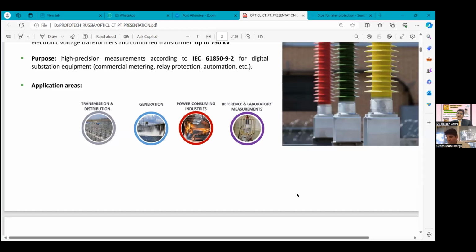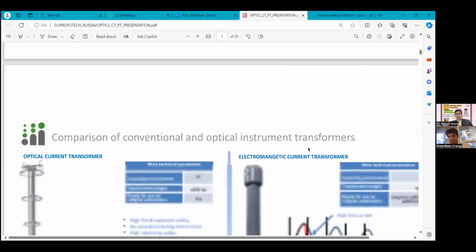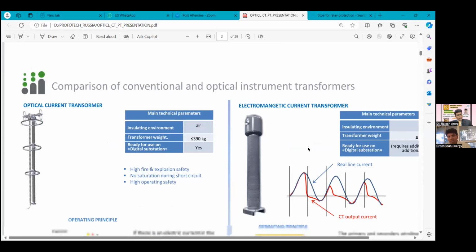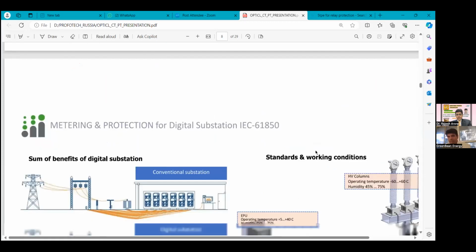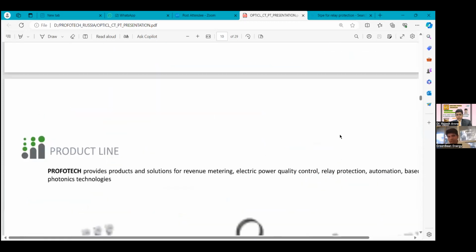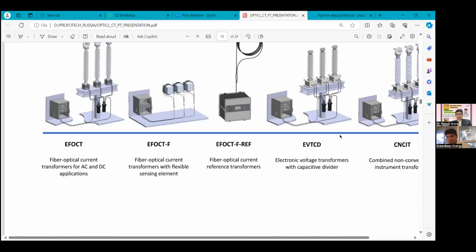And what about the short circuit level? How to ensure the short circuit capability of the CT? In our system the short circuit level has increased, and it has gone up to 63 kiloampere. This can measure 190 kiloampere, so it can withstand the short circuit very well. Apart from that, they have already done a short circuit test in Russia, and I'll show you the report.